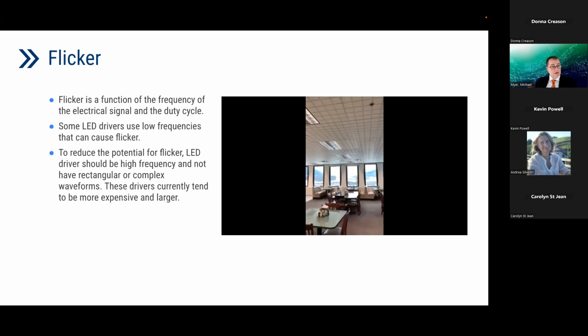The lighting industry is working on flicker. This was a problem when fluorescent technology was introduced in the early 80s, and they moved away from magnetic ballast to electronic ballast to solve some of those problems. Some of that same research is being applied to LEDs. To reduce flicker, you're really going to be looking at higher frequency LED drivers, and there's some other subtlety to it. The guide walks you through everything you should think about, at least at a preliminary level.